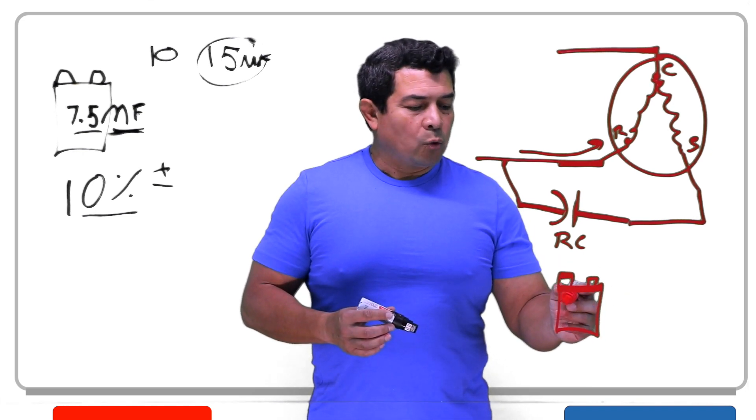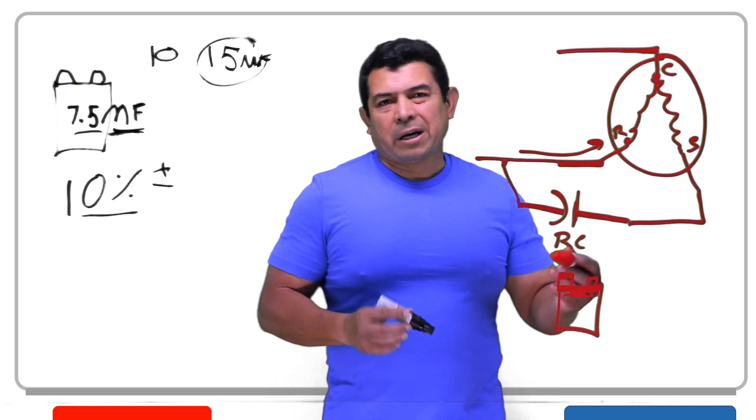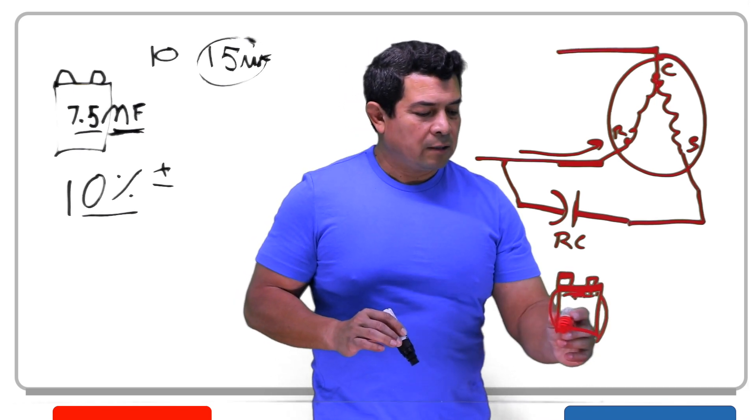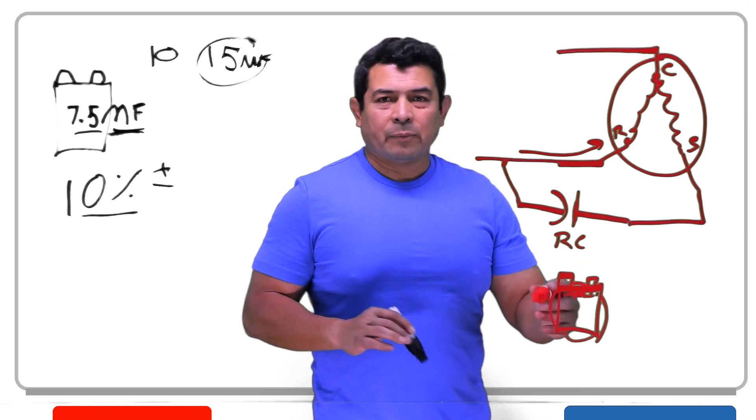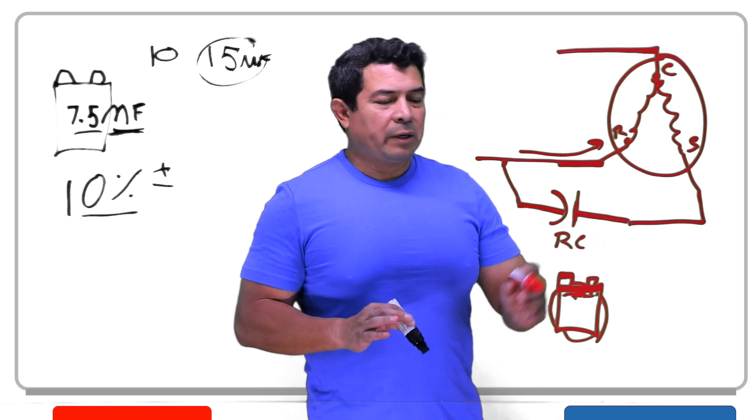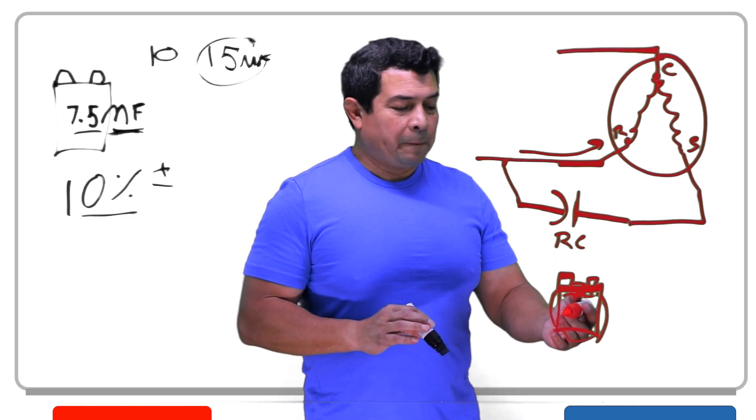If there's oil that is on this capacitor, if there's oil on it, the capacitor is just bad, don't even worry about it. If this capacitor has gotten swollen, because I've seen capacitors just swelled up, the capacitor is bad. Don't even bother testing it. You just put a capacitor back in there.